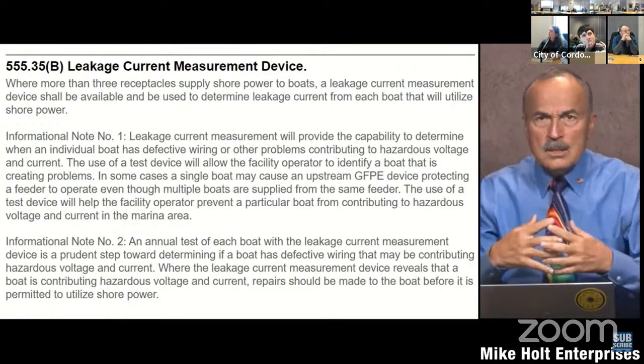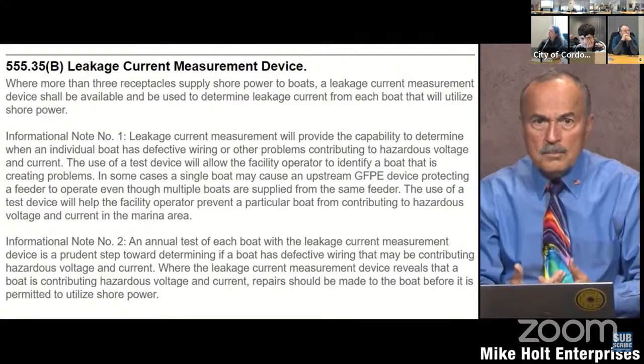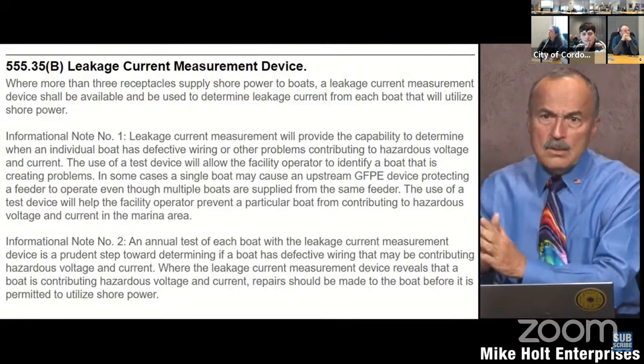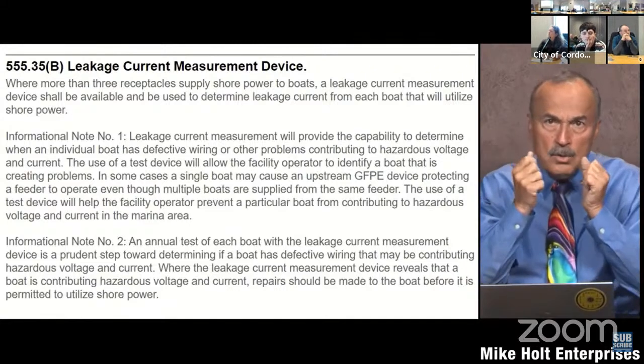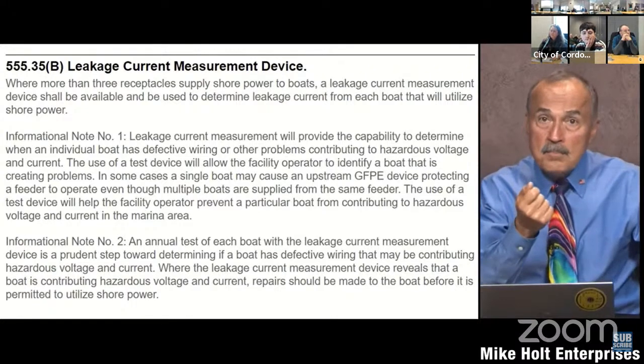But this is an overreaction of the code panel because people are terrified of people getting killed in the water, saying, let's get a recording, or let's get something that can measure these things. Let's find out which is the guy that's the problem. Well, you can find out which is the guy that's the problem. Just plug them in. Turn off all 4 receptacles, right? Turn on one at a time. Do they trip? No. Turn on the other one. No. No. Okay, so none of the boats are the problem. Turn them all on. Well, now it's tripping at 100 milliamperes. More than one boat is the problem.